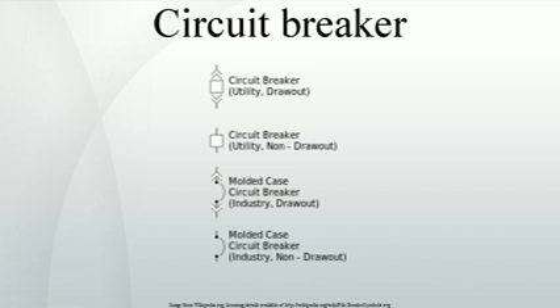Operation. All circuit breakers have common features in their operation, although details vary substantially depending on the voltage class, current rating and type of the circuit breaker. The circuit breaker must detect a fault condition. In low-voltage circuit breakers this is usually done within the breaker enclosure. Circuit breakers for large currents or high voltages are usually arranged with protective relay pilot devices to sense a fault condition and to operate the trip opening mechanism.